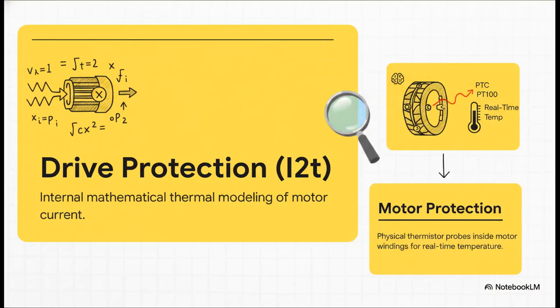So, to really protect a motor, we first have to understand how the drive actually thinks about heat. Heat is, without a doubt, the ultimate enemy of electrical windings. Luckily, modern VFDs have some pretty clever ways of dealing with it. The most important thing to grasp here is the difference between the drive calculating heat and the drive measuring heat. Drive protection uses what we call an I²T model. This is pure math. The drive is essentially looking at how much current the motor is pulling over time and calculating a simulated thermal state.